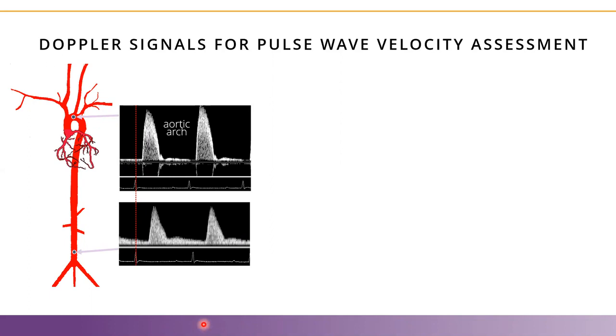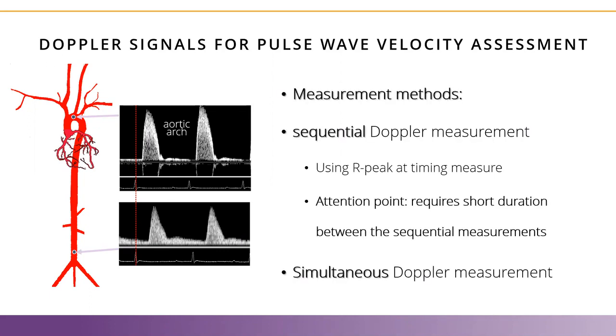And here you see the ECG signal R peak at the aortic arch and the abdominal aorta flow velocity. And you will clearly see a distance between these two peaks. And this is what is important in the pulse wave velocity measurement. So there are basically two ways to assess pulse wave velocity. In a sequential way, where you are dependent on your R peaks to do the timing, as well as a simultaneous method. Important part in the sequential measure is that you are really dependent on your R peaks.